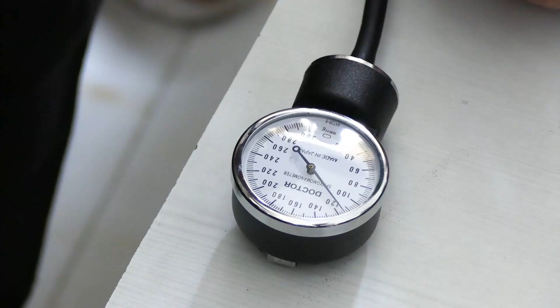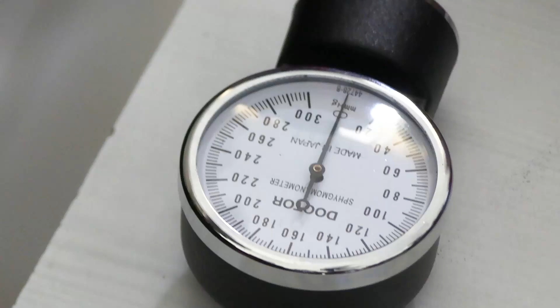Just remember, in this graduated sphygmomanometer, the readings are at a minimum spacing of 2. After 110 it is 112, then 114, 116, 118. Although blood pressure can theoretically be an odd number, with these instruments you have to speak of even numbers, because the graduations are like that. You can speak of 114 or 116, but not 115, as graduations are not there. So, the pulse was again felt at 110 or 120. So, the systolic blood pressure is 120, but the reading somewhat differs in auscultation. It may be 10 to 20 above what was noted in the palpatory method.